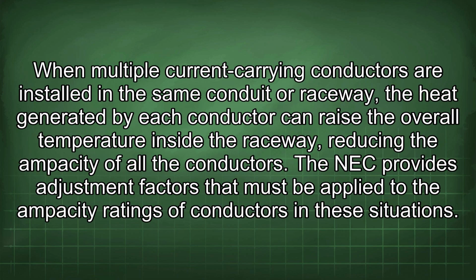When multiple current-carrying conductors are installed in the same conduit or raceway, the heat generated by each conductor can raise the overall temperature inside the raceway, reducing the ampacity of all the conductors. The NEC provides adjustment factors that must be applied to the ampacity ratings of conductors in these situations.